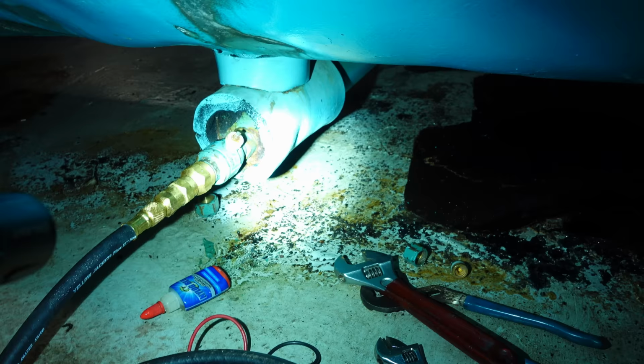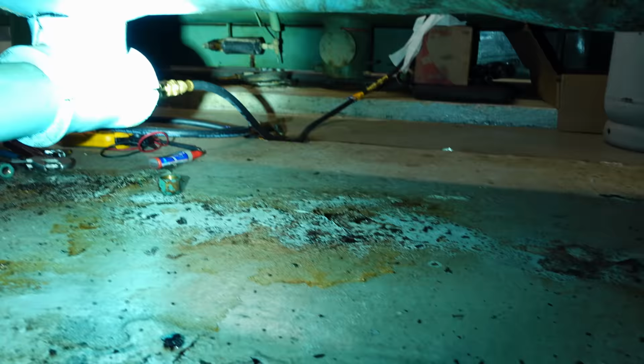We should have liquid up to this point unless... So that valve's open. Unless that's... Is that a check? That wasn't supposed to be a check. Surely that's not a check valve. Okay, well now we understand we're not getting liquid to our pump. So that makes sense. Come over here. This looks fine. The position, which is where it sits, why would we not be pushing it down?